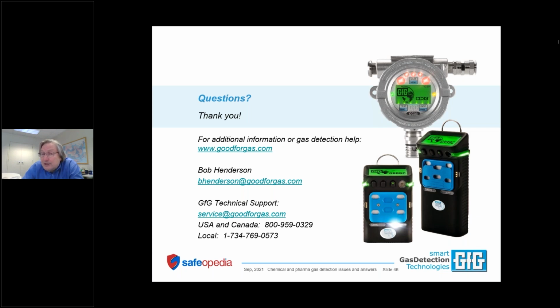If you're at a petrochemical plant where you've got a shutdown coming up, we've got large customers with 50 or 100 instruments, and they will set them up with a certain slate of sensors for a certain mission. And when they have a different shutdown, maybe they will use a different slate of sensors. So that's a great time to change the sensors. But generally, you're probably going to be better off putting the most commonly used sensor into the multi-sensor instrument and keeping the less commonly used sensors in a separate single sensor instrument, or have a multi-sensor instrument with a different configuration of sensors. I think that's about it.